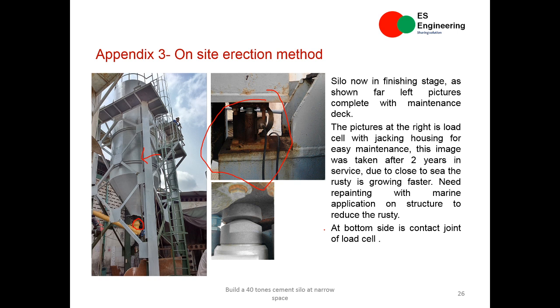So it means I have to do cornering. Let's say one load cell gives only 1.5 millivolts, and another load cell maybe not 1.5, but let's say 1.4. So I need to do cornering. But if 3 load cells are good and 1 load cell has a bad reading, that's not good. It means not all of the load is actually distributed to the 4 load cells. But at the time it was quite good, so the trimming at the load cell junction box was not so difficult.